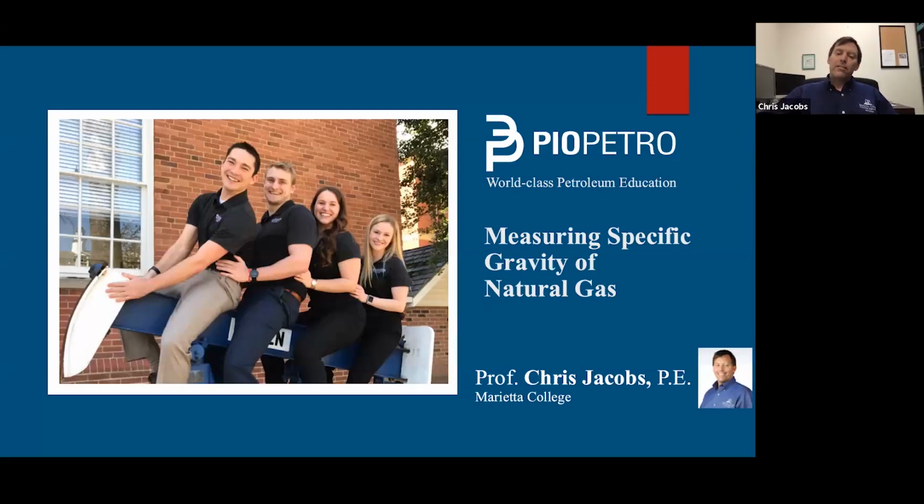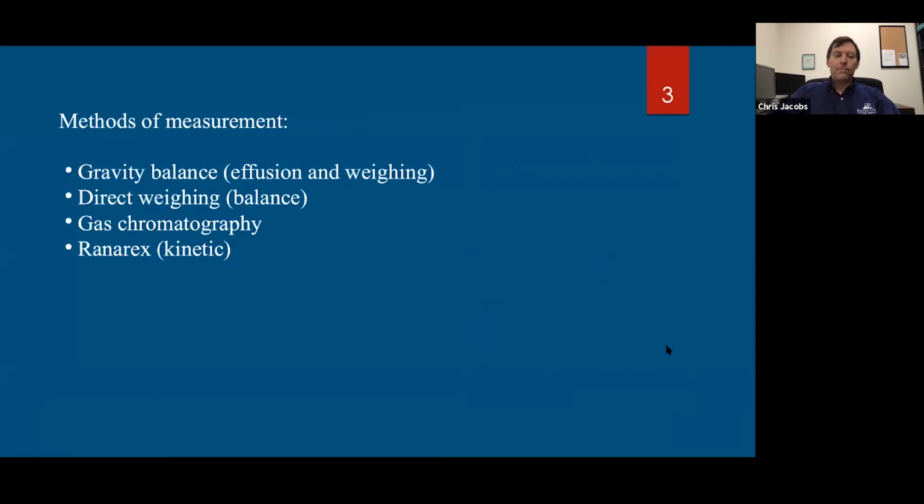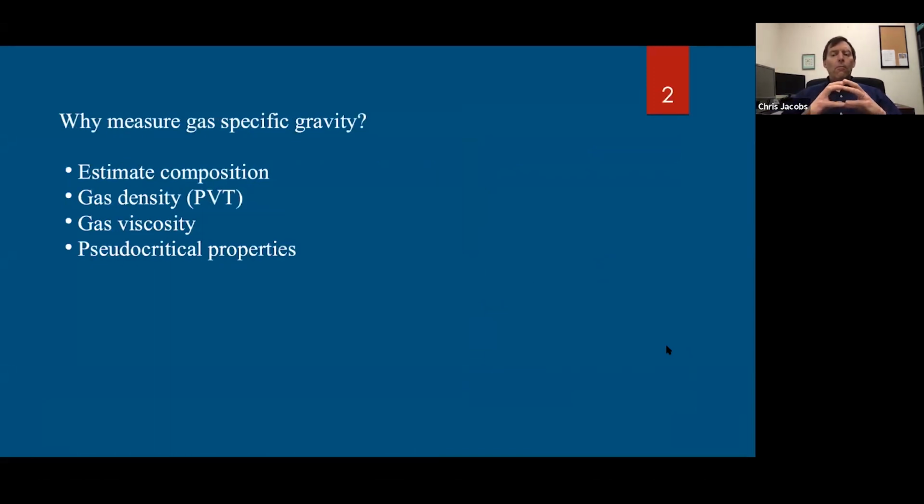As we mentioned, we are going to talk about measuring the specific gravity of natural gas. Okay. So why do we want to measure specific gravity of natural gas? What's the purpose? What can we gain from it? Well, I listed 4 things we can learn if we know the specific gravity. One of them is the gas composition. We can estimate the gas composition.